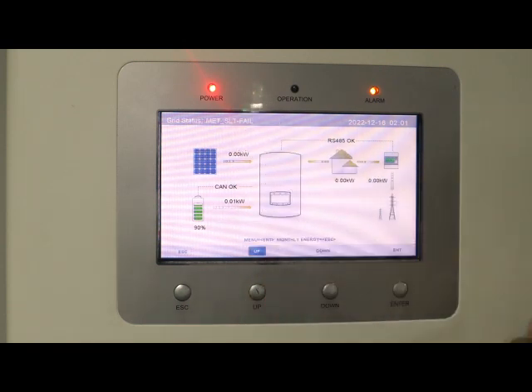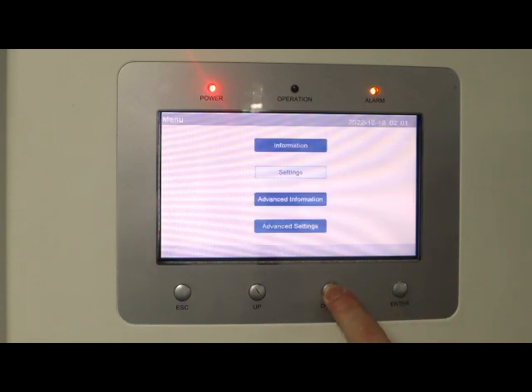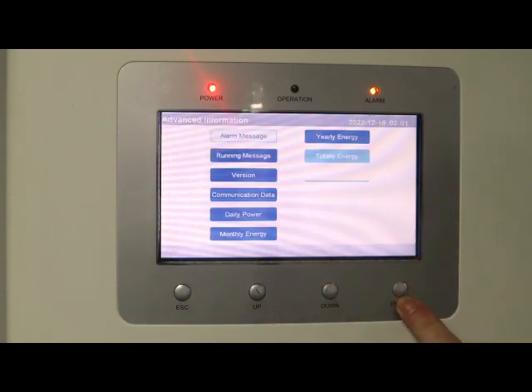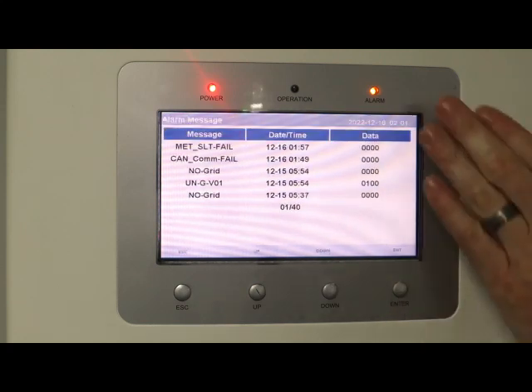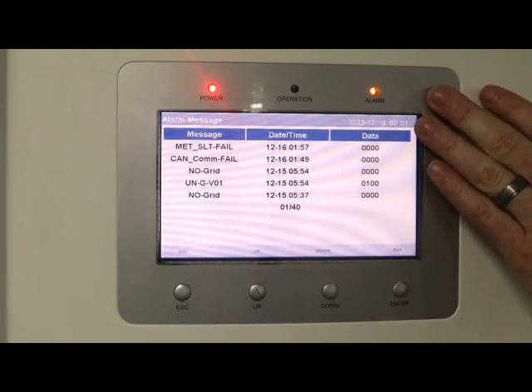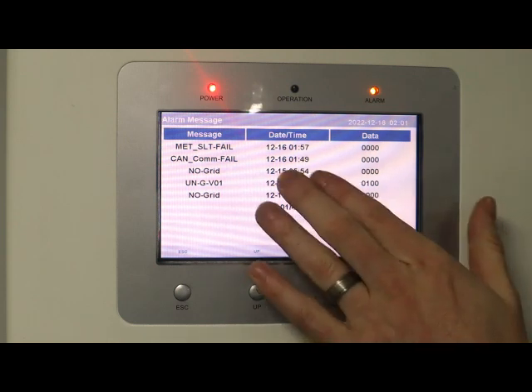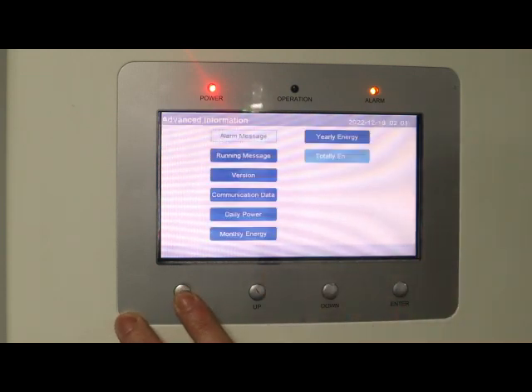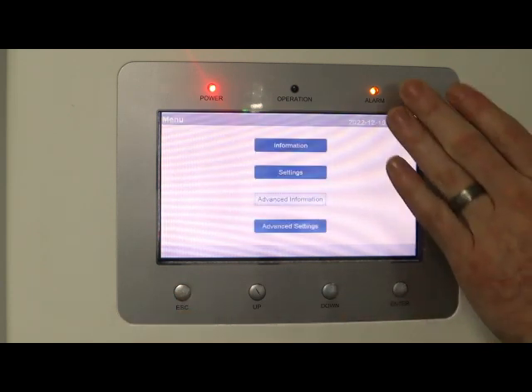The other place you can find it is in menu, advanced information. Press enter, go to alarm message, press enter, and at the top there you've got meter select fail with a date-time stamp. To get out of that, you press escape, press escape again.